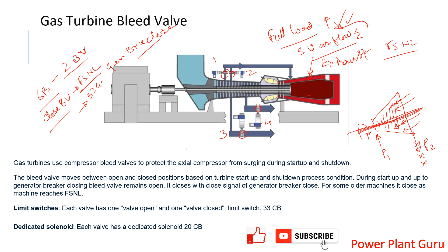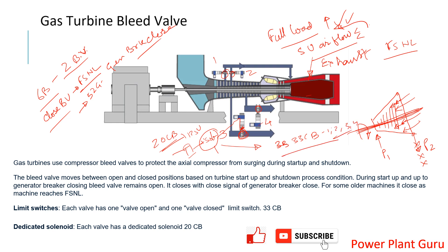Looking at how the valve operates: the solenoid valve is SOV 20CB. Air is supplied from the turbine itself, passing through a filter to a solenoid valve, which receives a 125-volt DC electric signal from the turbine controller. This pneumatic system actuates a plunger to operate the bleed valve. Once operated, position feedback is seen on 33CB — contacts one, two, three, four — and that is how the entire system works.